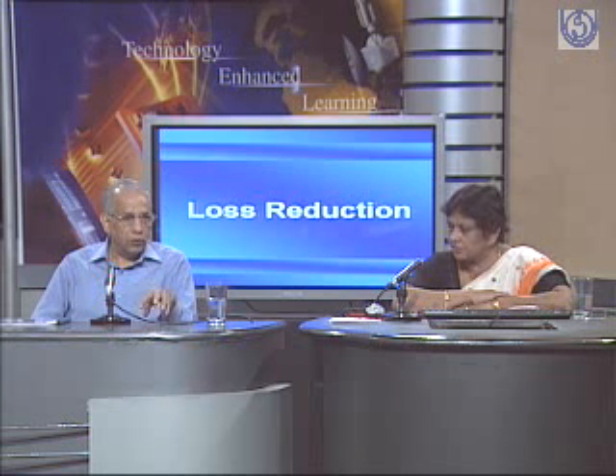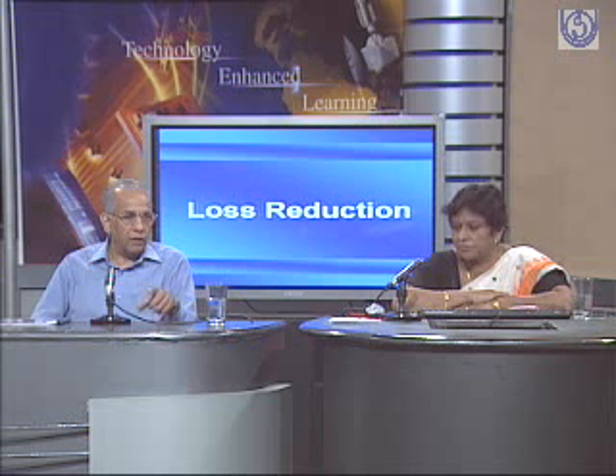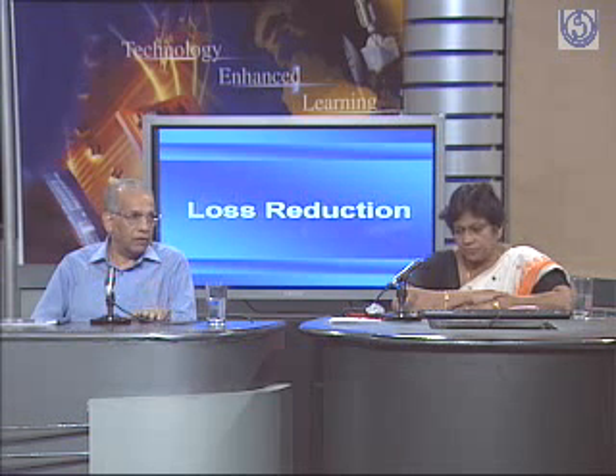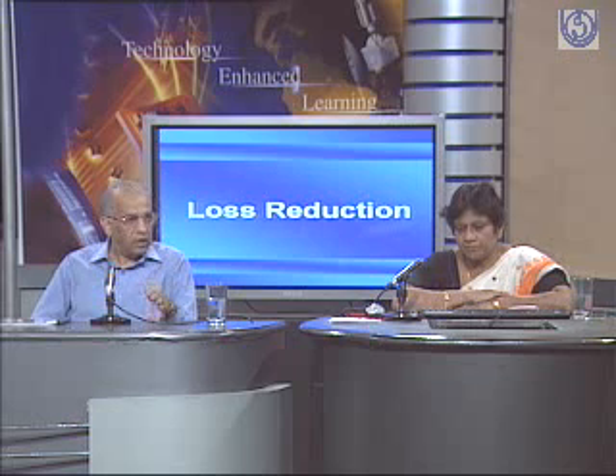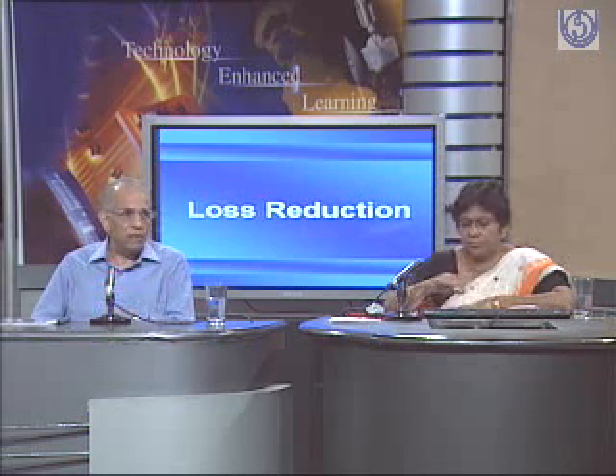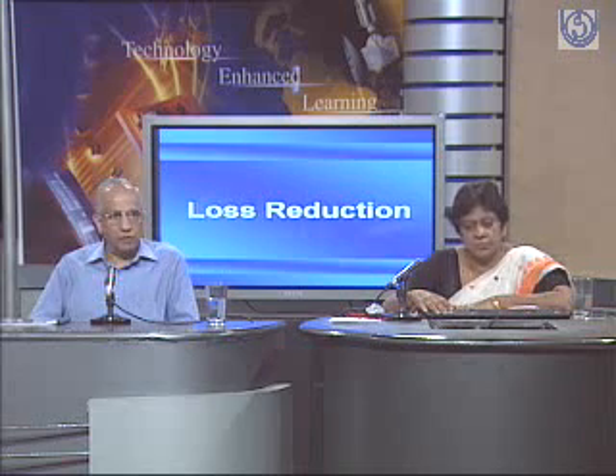So we have to consider that load. Exactly. So you size the transformer accordingly, because it is not usually feasible to change it that frequently. Suppose you find your transformer is getting overloaded, you don't just change it. So theft is a separate part, and sizing of the transformers and lines is a separate part. Okay, you can go ahead.